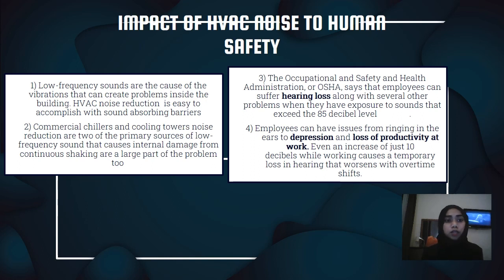Okay, firstly I will explain about the impact of HVAC noise on human safety. Low frequency sounds are the cause of vibration that can create problems inside the building. HVAC noise reduction is easy to accomplish with sound absorbing barriers. And then commercial chillers and cooling towers are two of the primary sources of low frequency sound that causes internal damage from continuous shaking, which is a large part of the problem too.